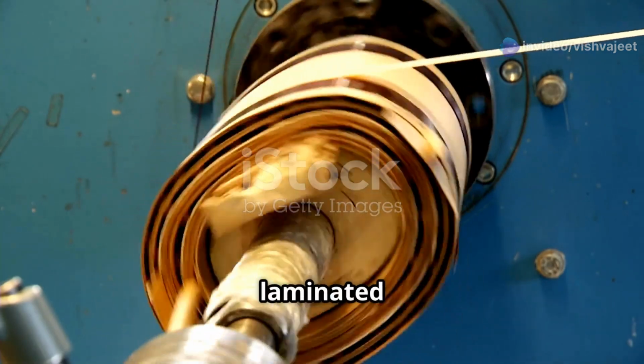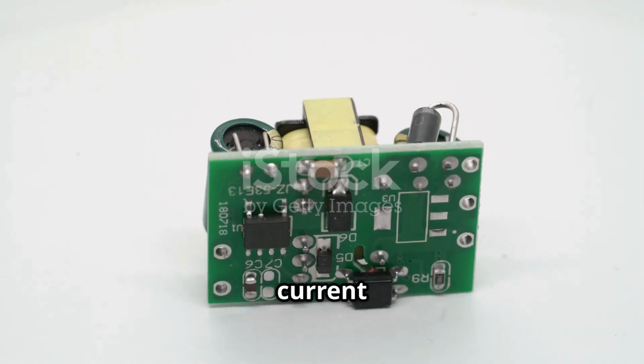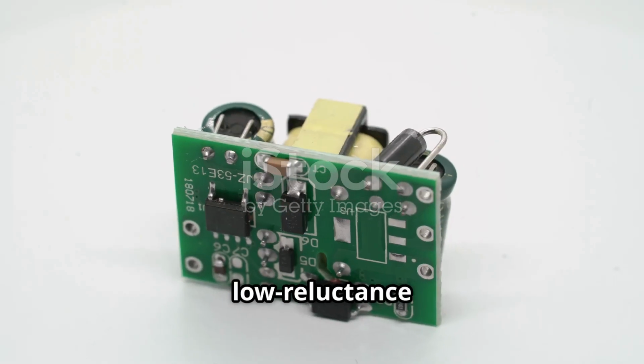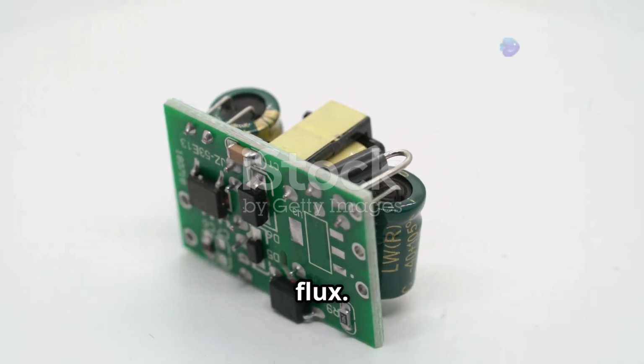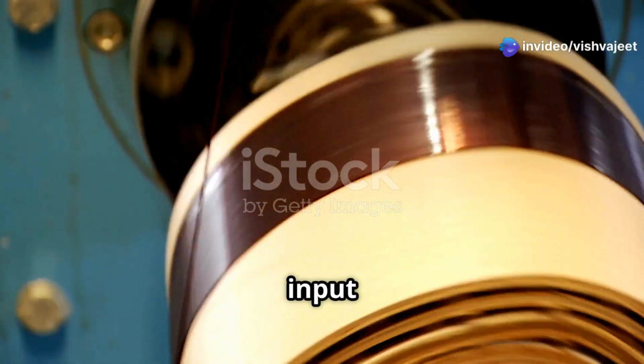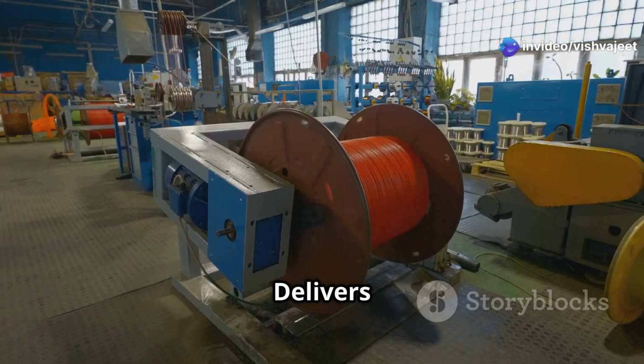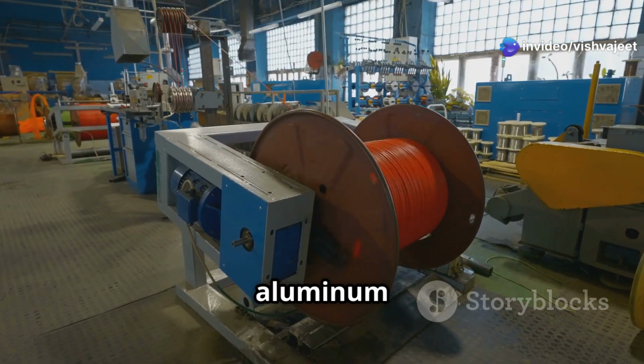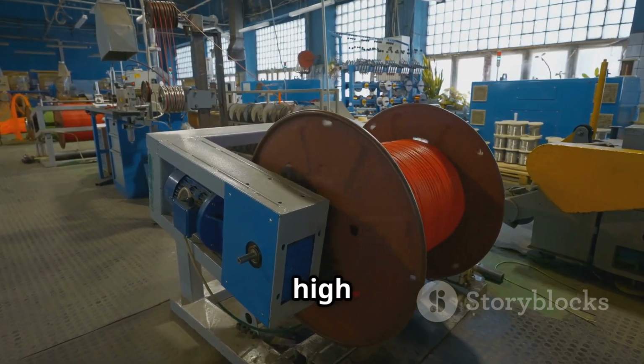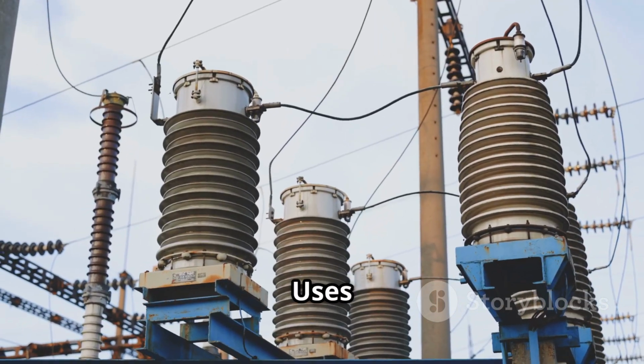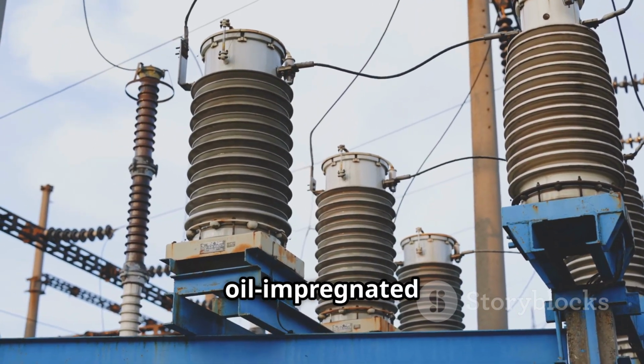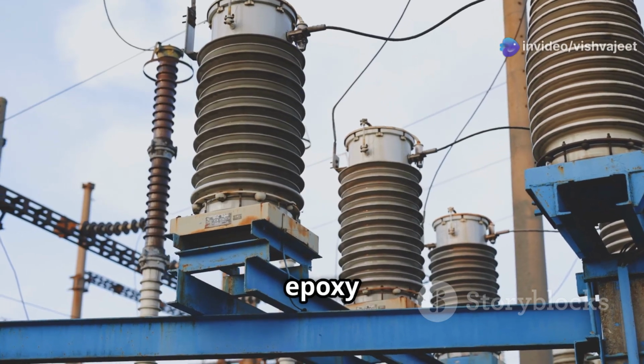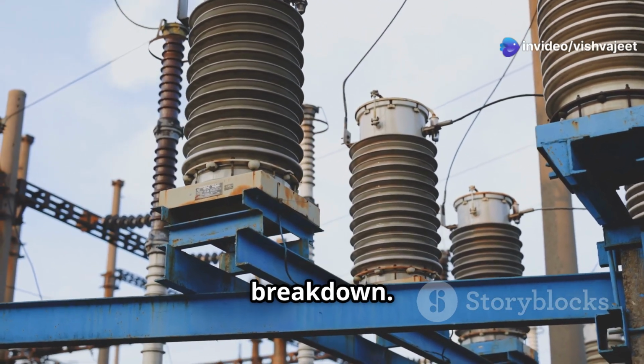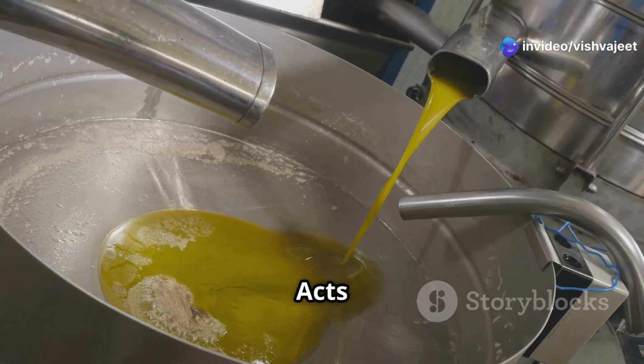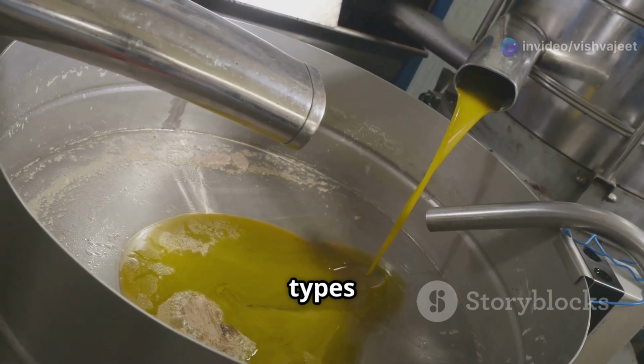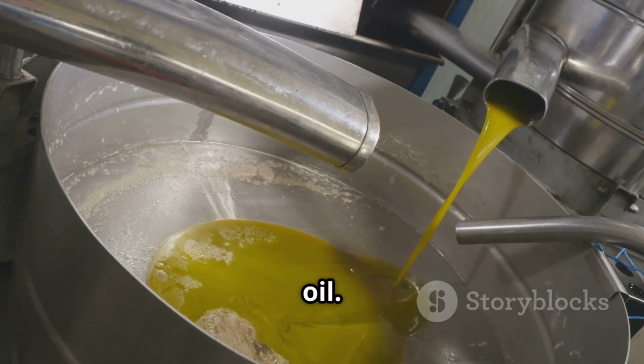Core: made of laminated silicon steel to minimize eddy current and hysteresis losses, it provides a low reluctance path for magnetic flux. Windings: the primary winding receives input power, and the secondary winding delivers output power, made of copper or aluminum conductors insulated to withstand high voltages. Insulation uses materials like oil-impregnated paper, porcelain, and epoxy resin to prevent electrical breakdown. Transformer oil acts as an insulator and coolant. Common types include mineral oil and silicone oil.